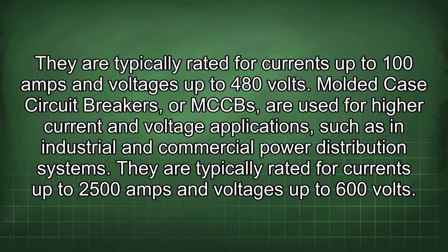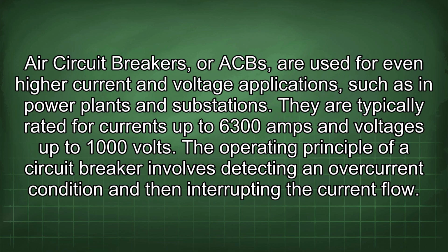Molded case circuit breakers, or MCCBs, are used for higher current and voltage applications such as in industrial and commercial power distribution systems. They are typically rated for currents up to 2500 amps and voltages up to 600 volts. Air circuit breakers, or ACBs, are used for even higher current and voltage applications, such as in power plants and substations. They are typically rated for currents up to 6,300 amps and voltages up to 1,000 volts.